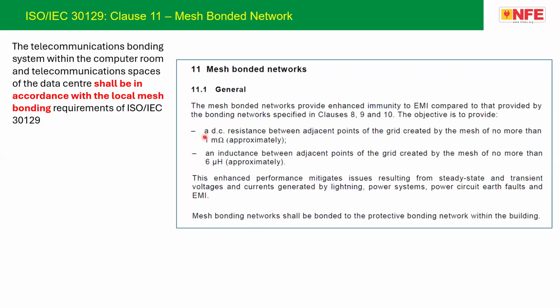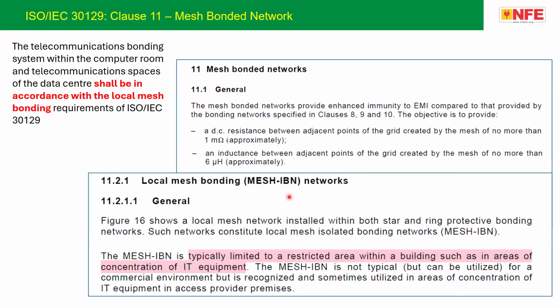The objective is to provide a DC resistance between adjacent points of the grid created by the mesh not greater than a few milliohm and inductance no more than 6 microhenry. Then it is classified into local mesh bonding network, which is called local mesh IBN. Mesh IBN is typically limited.